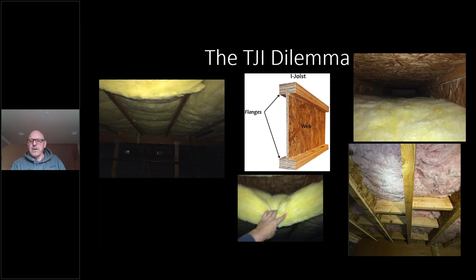So this house is 1,250 square foot. A typical home, if you're going to run a blower door on it, could be anywhere from 800 to 2,500 CFM 50. I mean, that's just a big number. 800, 900, 1,000 in the real world would be acceptable. So with the little bit of effort that we did, we were able to get our leakage down to 189.